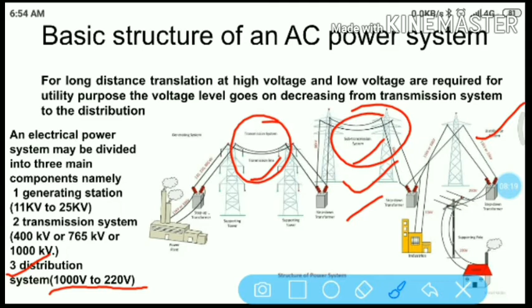Single line diagram representation. A single line diagram or a one line diagram is the essence of a system in its most simplified form. A power system basically consists of a set of generating units, a transmission network, and a combination of industrial, commercial, and residential loads. In an AC system, electrical energy is generated by three-phase synchronous generators, transmitted by three-phase transmission lines and distributed through three-phase networks. A balanced three-phase system is studied on a per phase basis. A single-phase circuit consists of one of the three-phase conductors and a neutral return conductor.